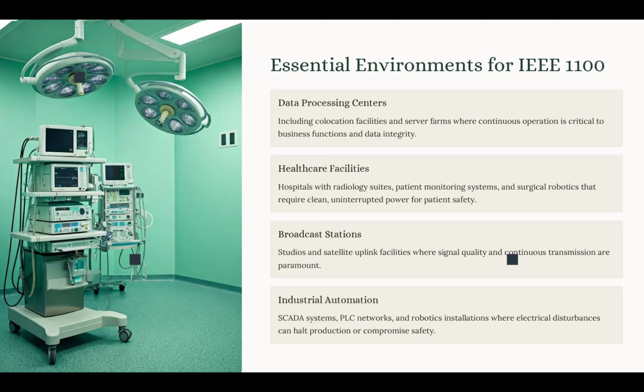There are very strict criteria when we are dealing with medical equipment. A clean power supply is also recommended, like a double conversion UPS system, so we make sure we have clean voltage. When we say double conversion, we mean we have AC, then we convert it to DC, store it in a UPS, and then when we want to supply the medical device, we convert it to AC again. So we basically isolate the distribution power grid from the equipment that is supplied by that power.